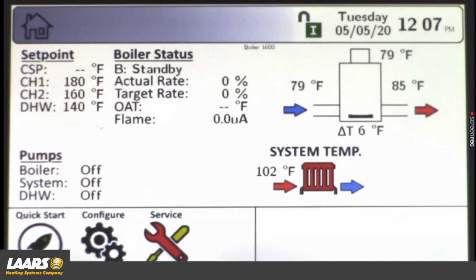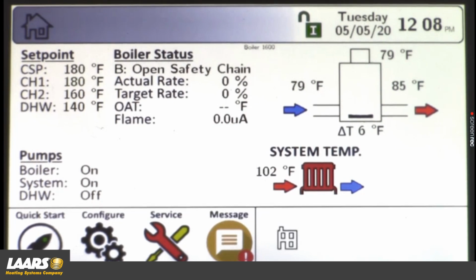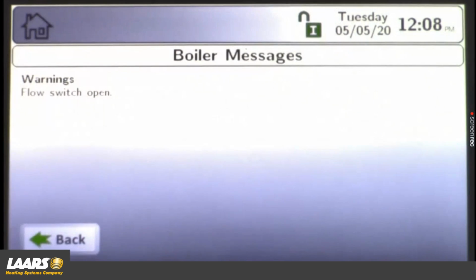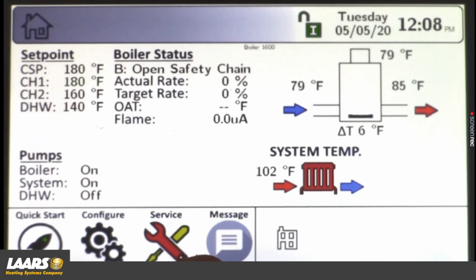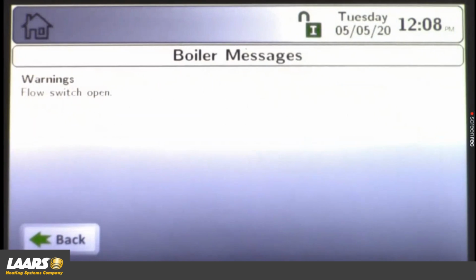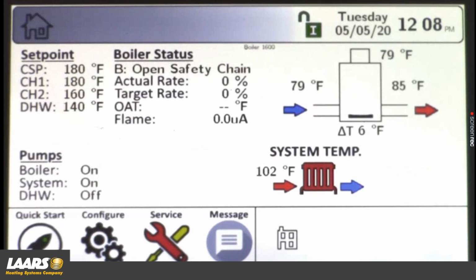All right, so next we're going to talk about service. But before I talk about service, I'm going to give this boiler a call for heat, and you'll see a message box appear. And anytime there's a message symbol, you can click on it and it will tell you what's going on. Example here, warning, the flow switch is opened. And when I go back to the home screen, that symbol is now in gray. That means somebody identified it or opened that icon, but did not correct the issue. So let's go back in now.